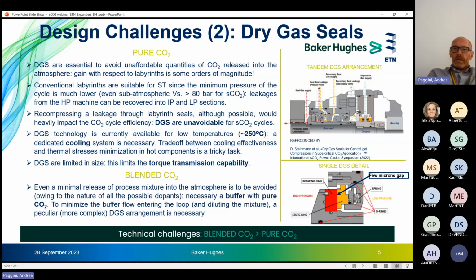Which are the peculiarities of the CO2 blended expanders? If you have pure CO2, in principle, you might even afford a minimal release, a minimal leakage to the atmosphere, just a few grams per second, since we are speaking of these numbers. But if you have blended CO2, all the possible dopants added to the CO2 in order to have the required shift of the critical properties are gases that should not be vented. So typically sulfur dioxide, titanium tetrachloride, hexafluorobenzene. So you need to have a buffer flow of pure CO2 in order to avoid such a leakage.